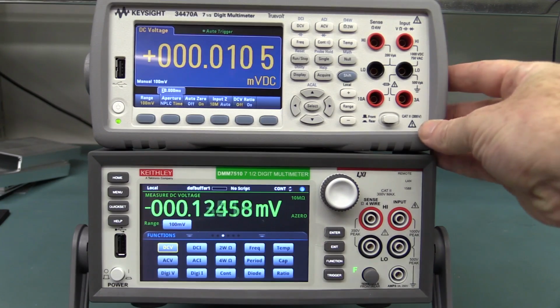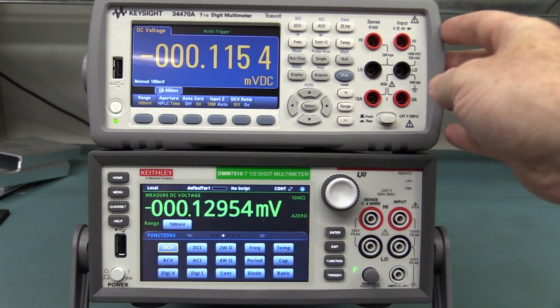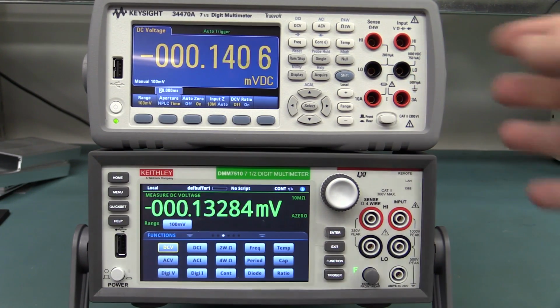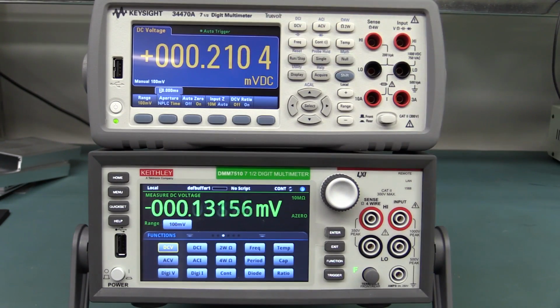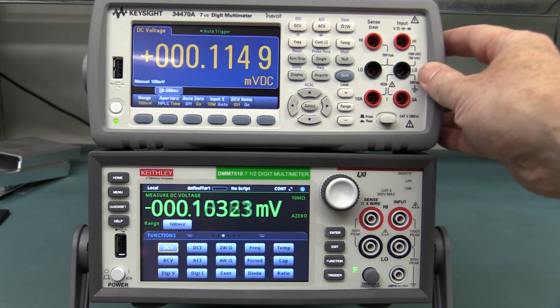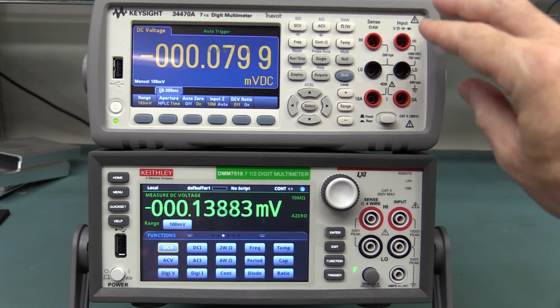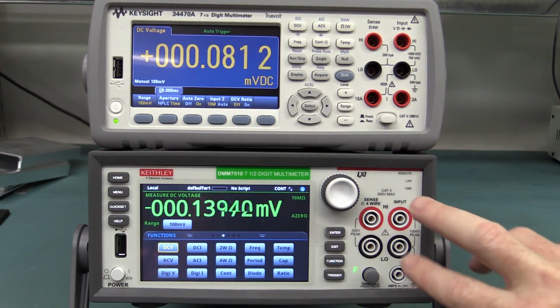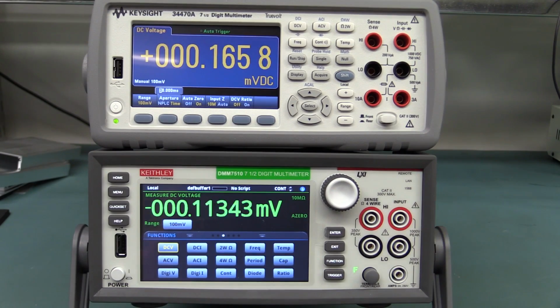The Keysight one is much cheaper. It's around $2,900, so you're saving $1,100 difference. It's also 7.5 digit, but it's not as fast. It's only 5,000 or optional 50,000 samples per second. This does 1 million samples per second.